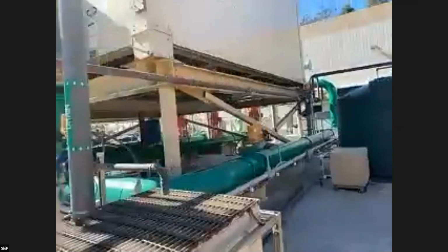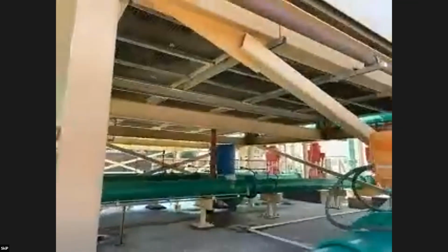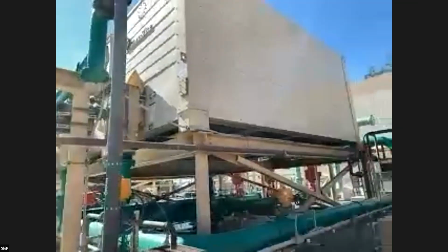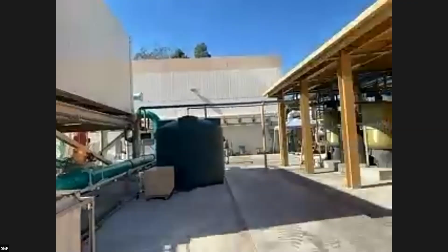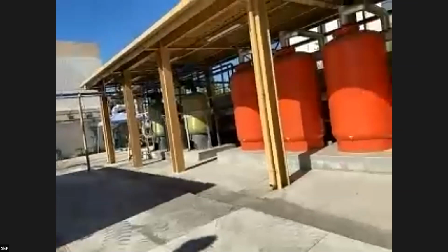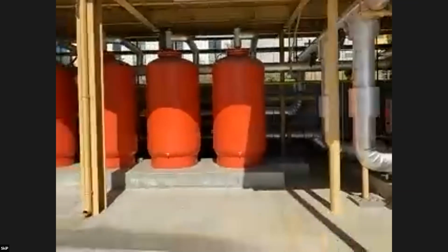What's happening is we're blowing cold air into the space. If we supply your space with 55-degree air and cool your classroom down to 72 degrees, then when things are balanced we should get about 73-degree air back out of the space. So we go in at 55 degrees and come back out at about 73. That heat we take out of the building goes into the water line and returns all the way back to the central plant, and then we have to get rid of that heat somehow. That's what the cooling towers are for.